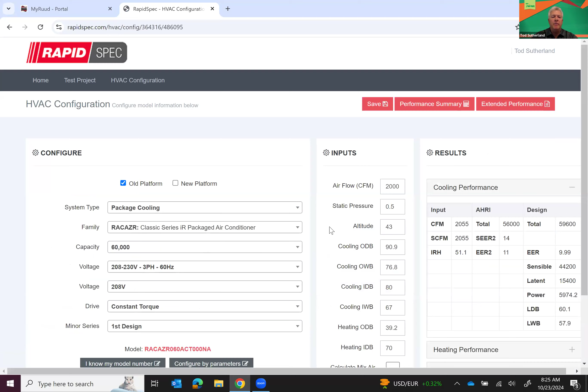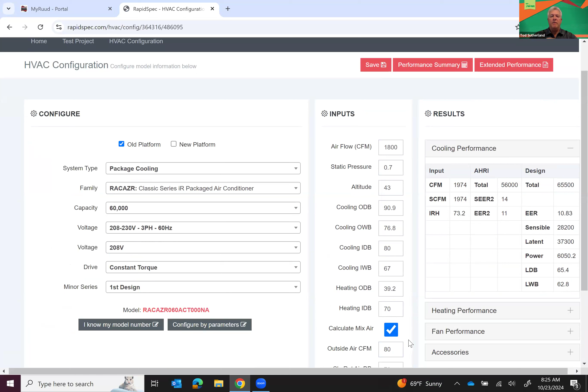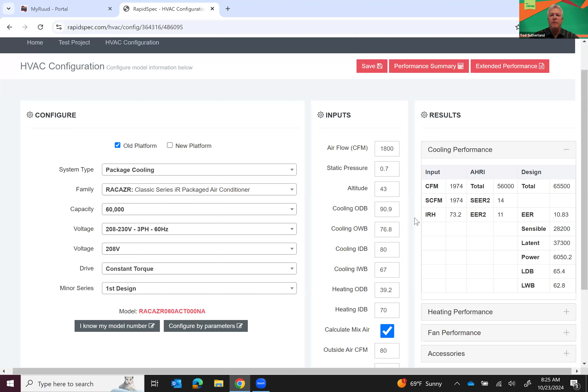And you'll see it's added it here. I can change this to 1, and I can change this to RTU6, then jump into details. It's going to populate all the same information, but I needed to do this one separately because on this particular one, the print was calling for 1800 CFM at 0.7 static pressure, and I needed to add mixed air of 80 CFM. So if those package units are all the same, great, but if you have one that's different, you can copy it, populate the information, change whatever's different, and hit save.